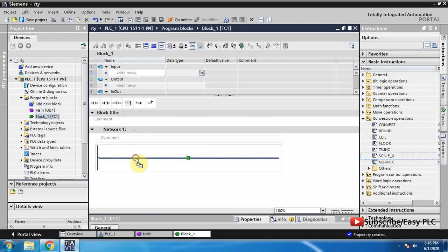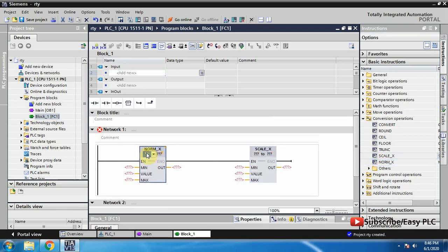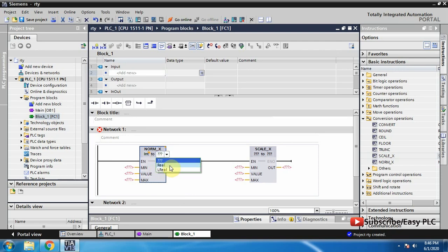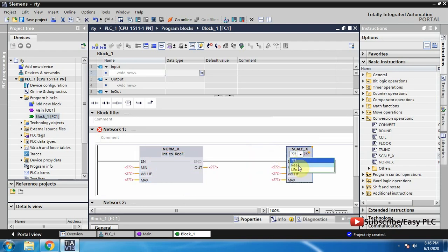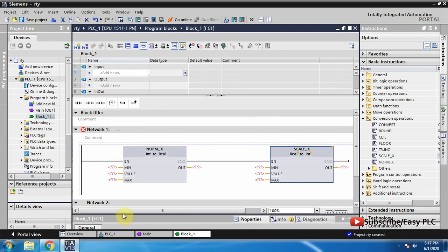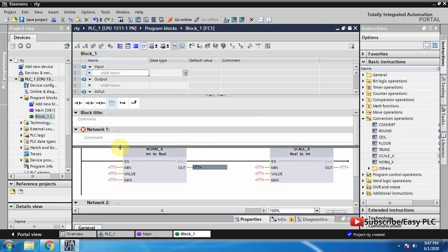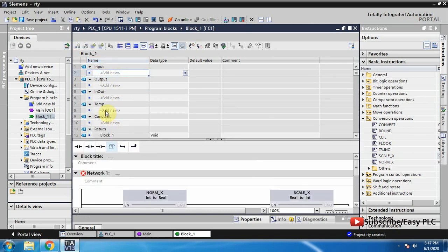We can make any program logic in this function. We will make an analog scaling function using NORM and SCALE instructions. As you can see, the NORM and SCALE instructions need to connect some tags. We can connect them directly here, or we can also create some tags within this function.